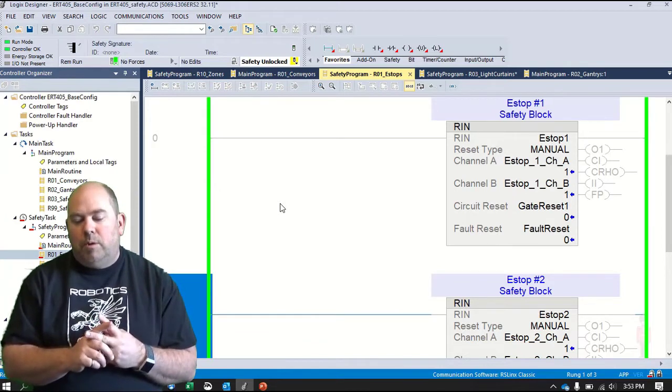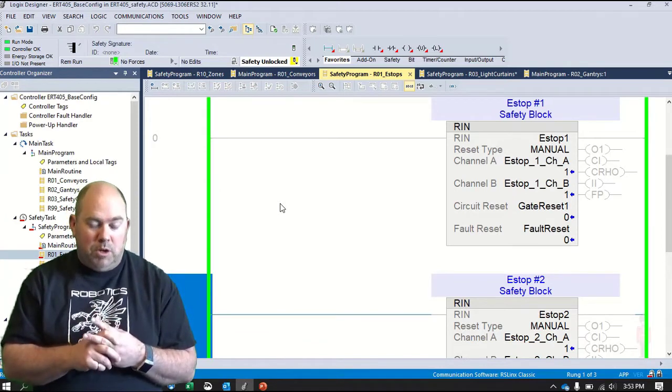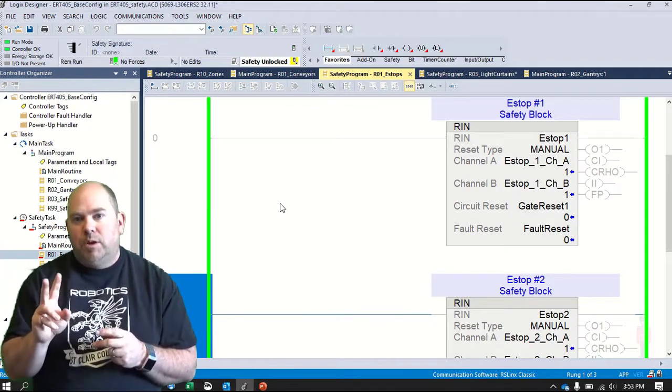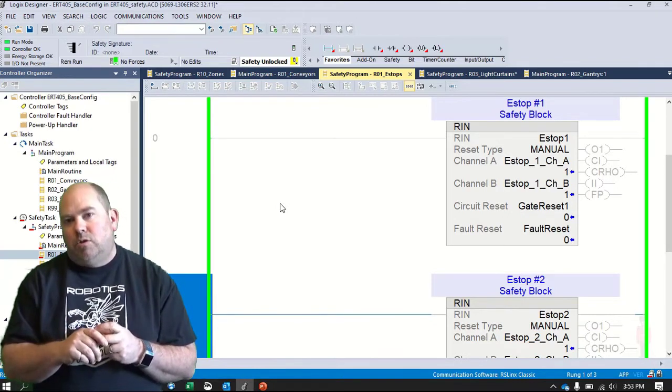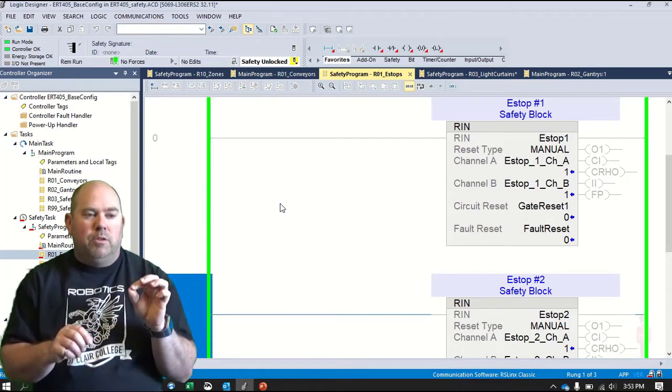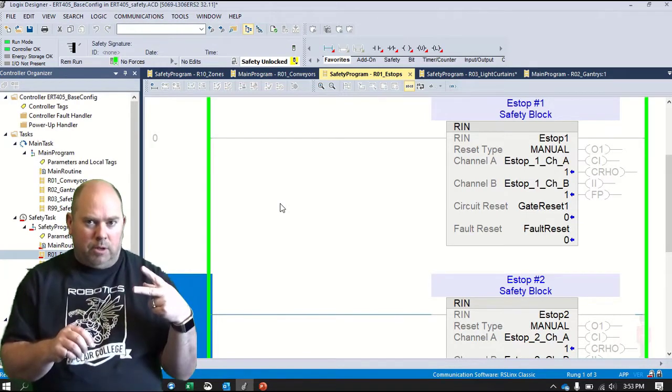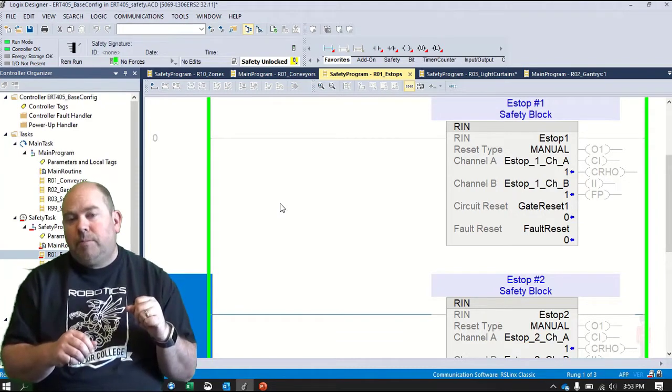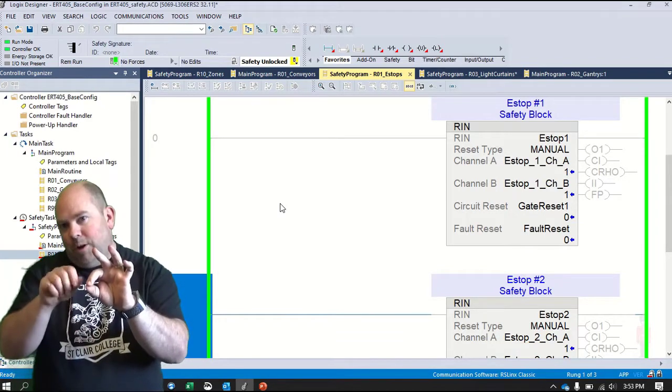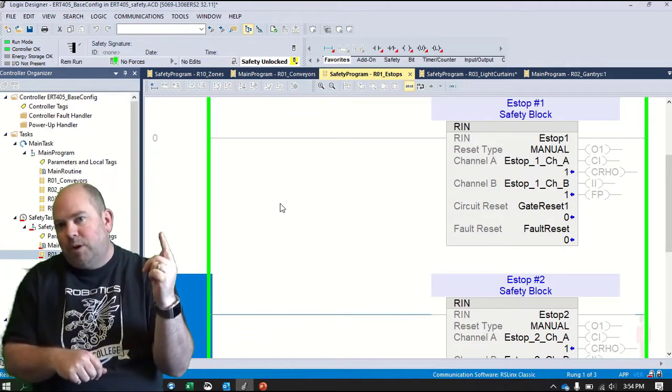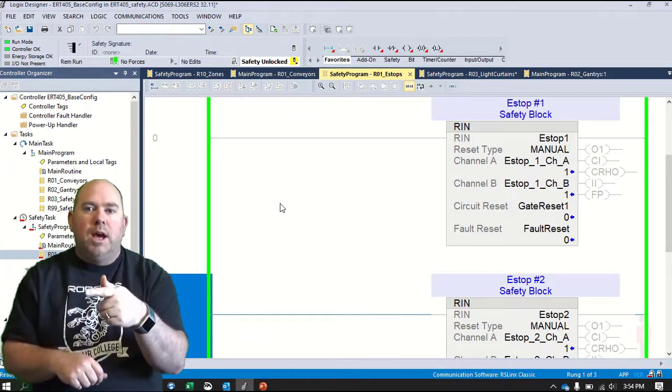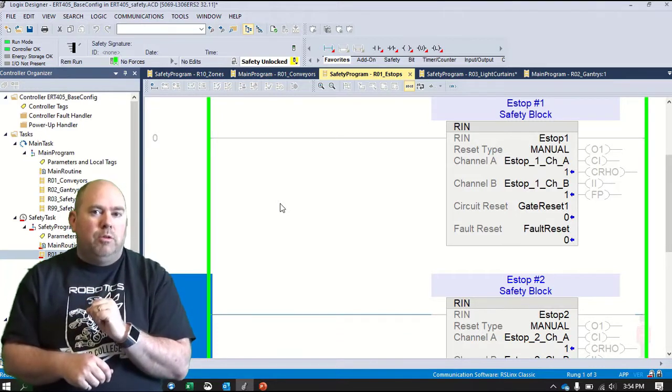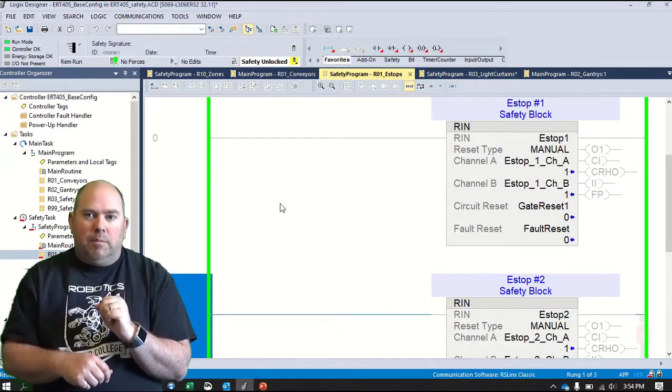So what you should be doing with these things is, because every device is a two-channel device, you should be going and actually removing wires from these devices. So there should be two wires, two input wires coming off of e-stop. You will take one wire, unscrew it, remove it, and once you remove it, the PLC should detect that a wire has been removed. And that block should go into a fault condition, right? Because now your two inputs do not agree.